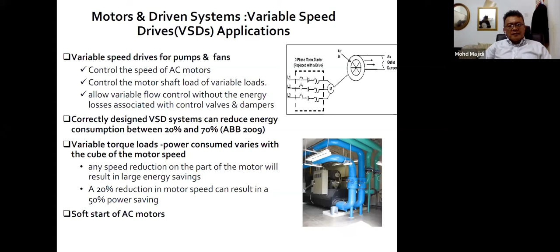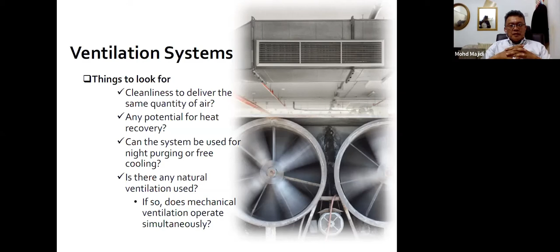In the ventilation system, check whether it is properly maintained and whether there's potential for heat recovery, since the chiller system provides excess heat that can be used to heat water for cleaning, kitchens, or showers in your buildings. Can the system be used for night purging or free cooling, cooling the building at night with cool outside air so demand the next day is much lower? Is natural ventilation being used? This is an option, and a requirement for certain green building standards.